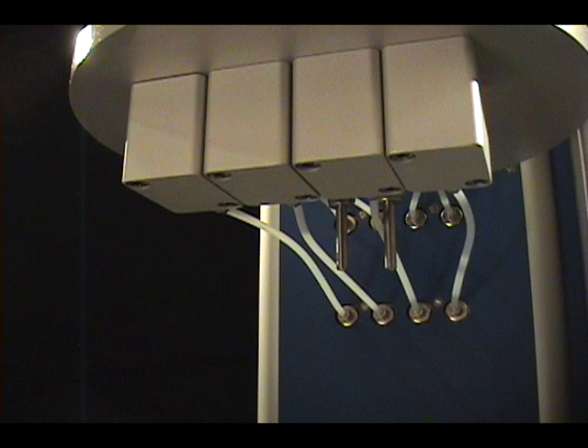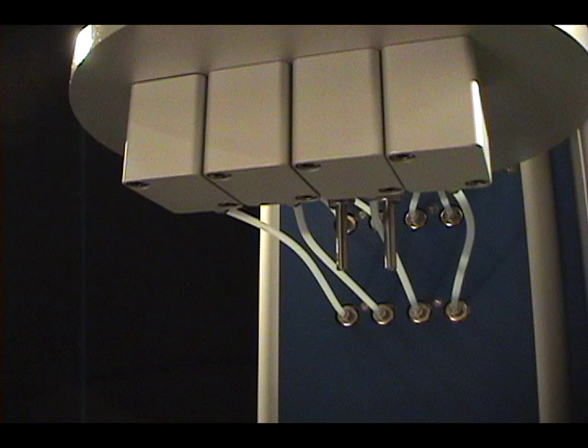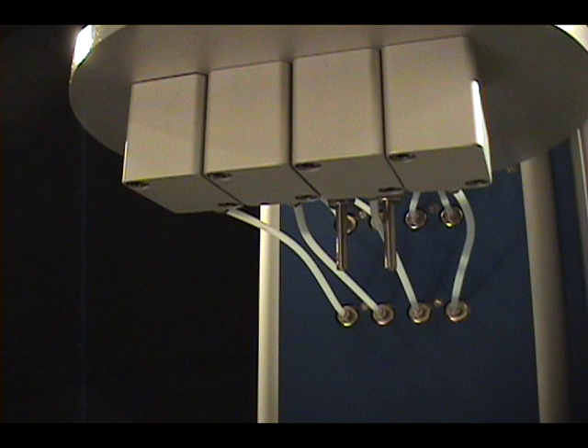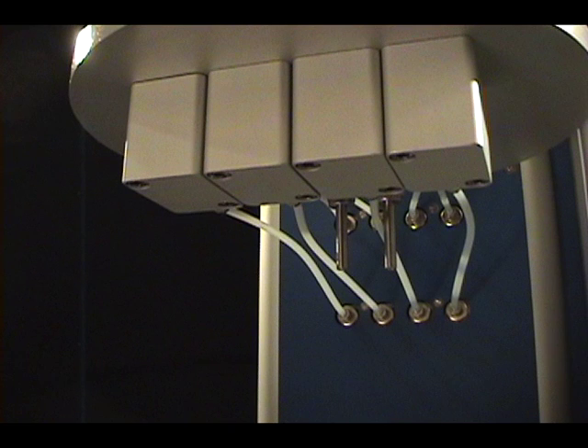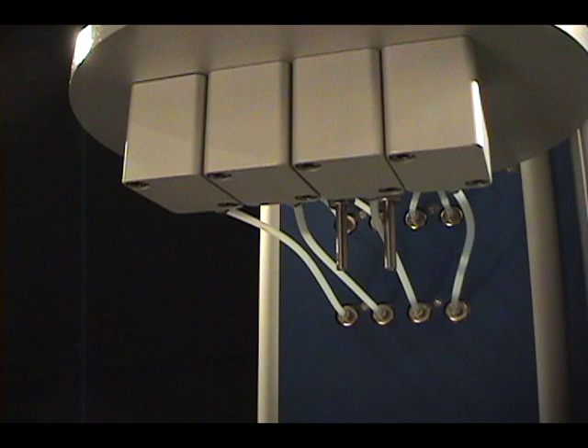On the underside of the bath, each tube has a corresponding aluminum mixing chamber, which ensures that the sample and the injected solvent are thoroughly mixed, preventing the sample from becoming solid as soon as it leaves the thermostatic bath.